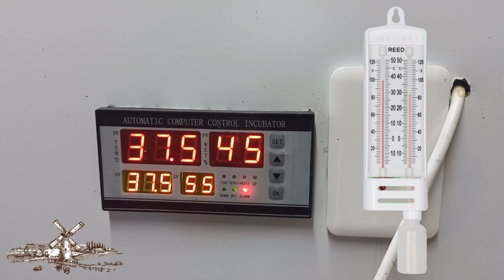And again, if you did this correctly, you would expect the humidity measurement to plummet down to 44%, which it does. And the controller has now figured out that the humidity is in fact too low. And so you will see that an alarm goes off to warn you about low humidity, and it turns on our wet heater in order to get the humidity up.